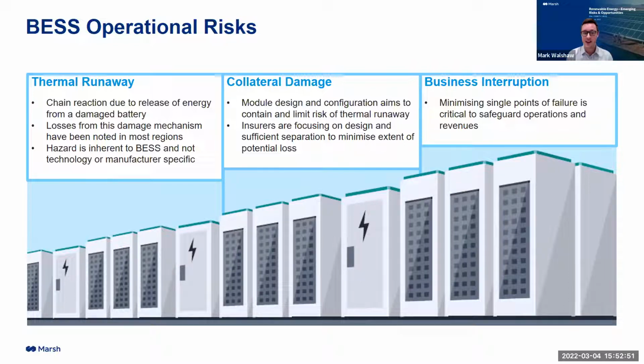When assessing the design of an installation, there has to be sufficient separation between each of the enclosures themselves, and minimum guidelines for this as per NFPA is around 3 meters. But what we're seeing in certain developers is separation of up to 7.5 meters being used to help mitigate that risk even further, going beyond those guidelines.